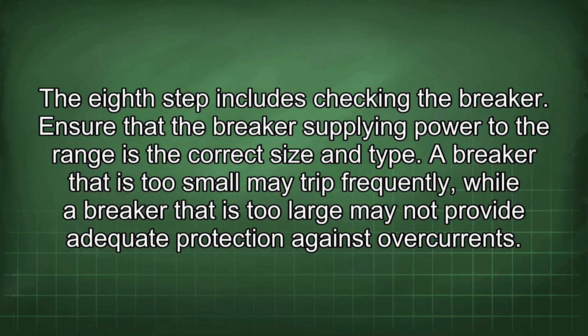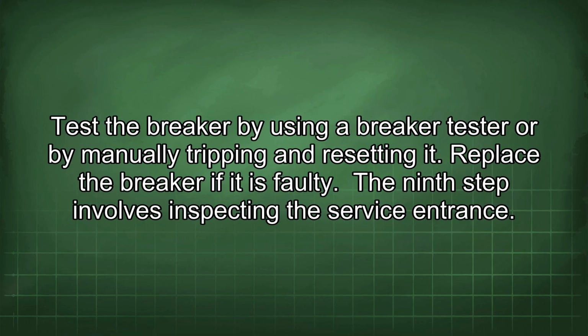Ensure that the breaker supplying power to the range is the correct size and type. A breaker that is too small may trip frequently, while a breaker that is too large may not provide adequate protection against overcurrents. Test the breaker by using a breaker tester or by manually tripping and resetting it. Replace the breaker if it is faulty.